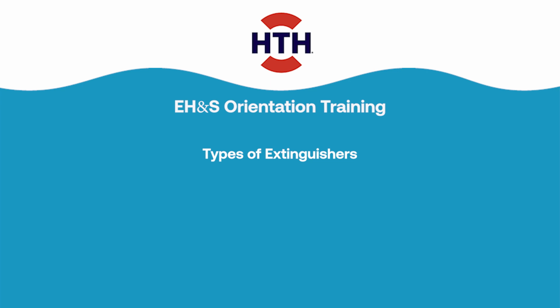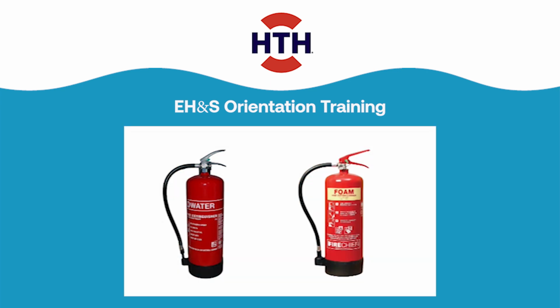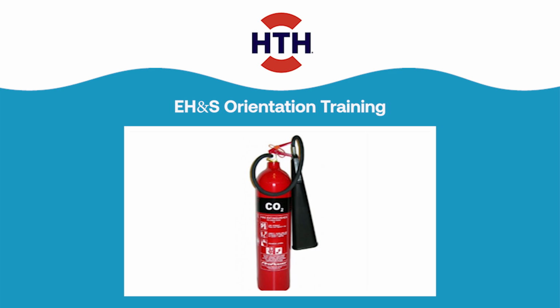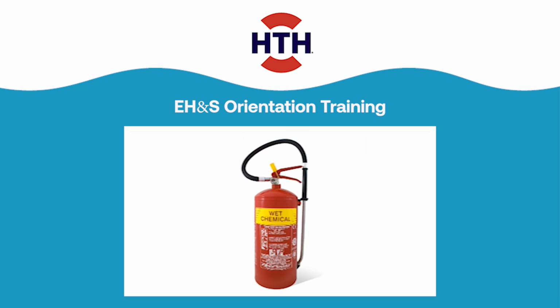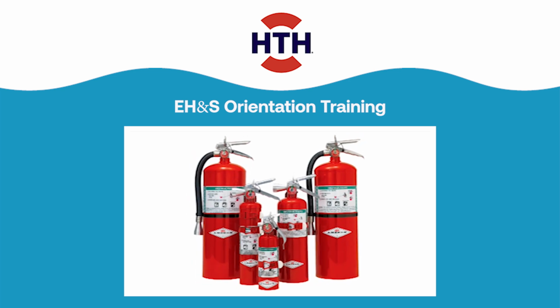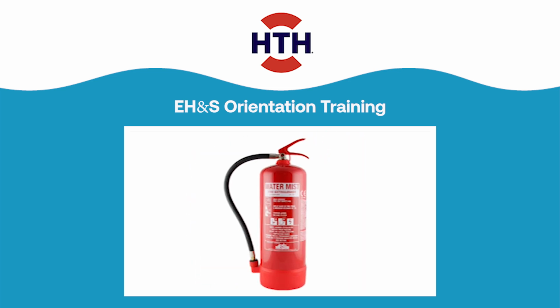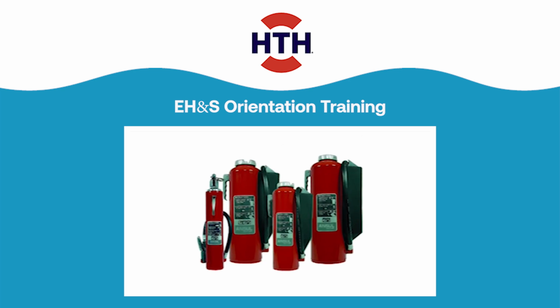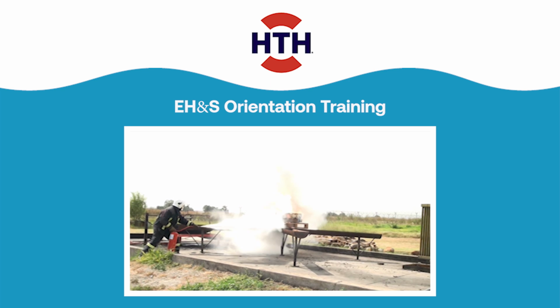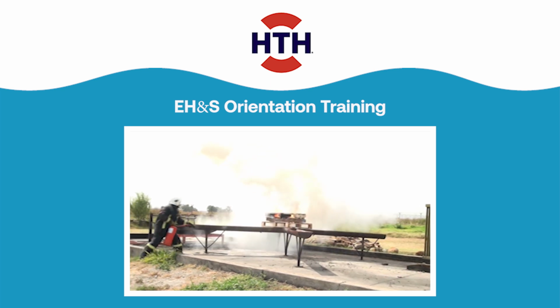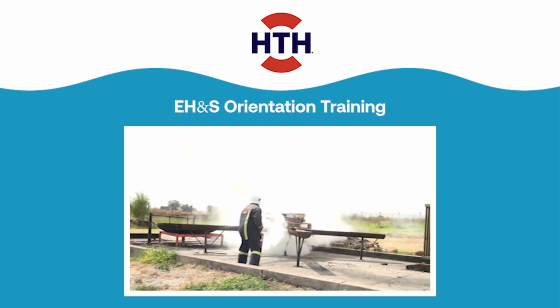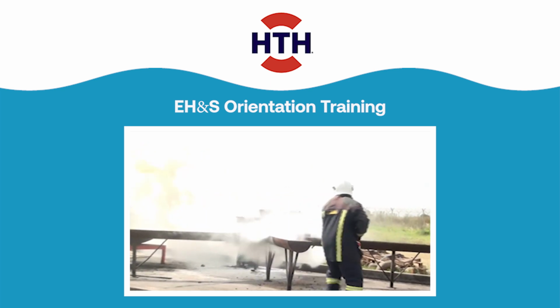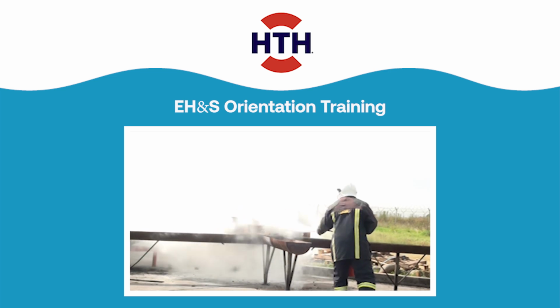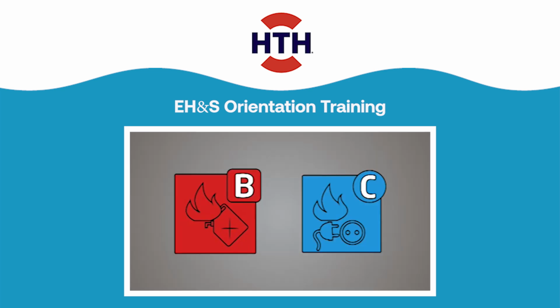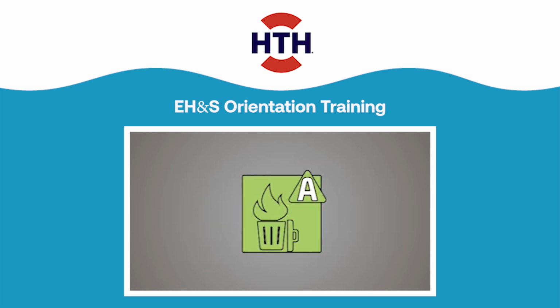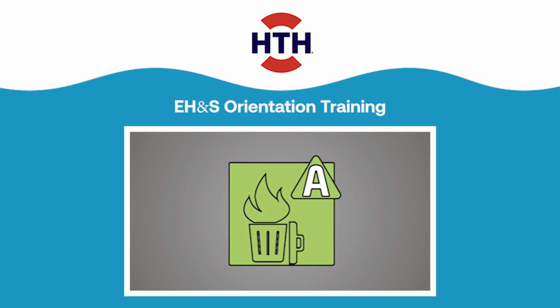Types of extinguishers: water and foam, carbon dioxide, dry chemical, wet chemical, clean agent, dry powder, water mist, cartridge-operated dry chemical. Carbon dioxide fire extinguishers extinguish the fire by taking away the oxygen element of the fire triangle, and also by removing the heat with a very cold discharge. Carbon dioxide can be used on Class B and C fires. They are usually ineffective on Class A fires.